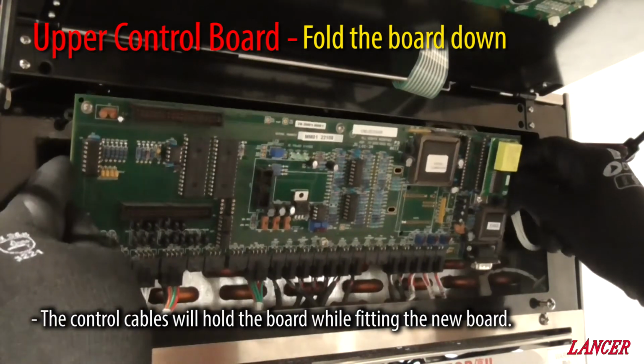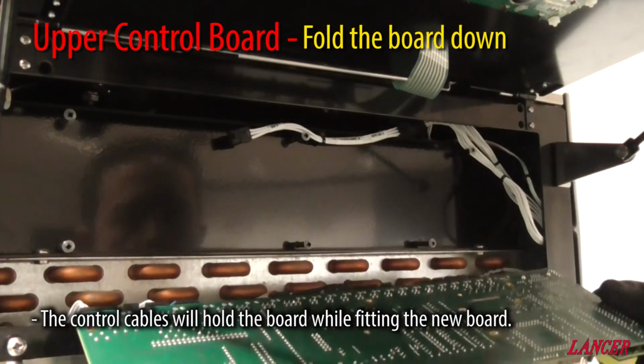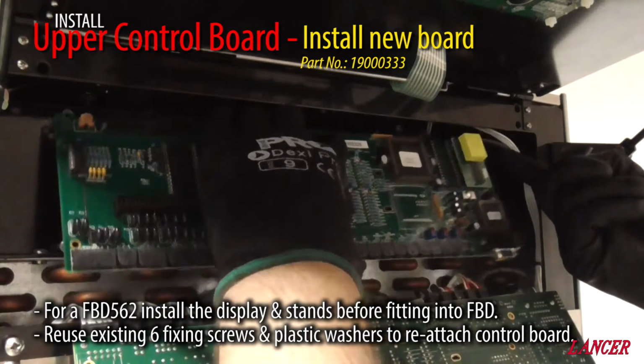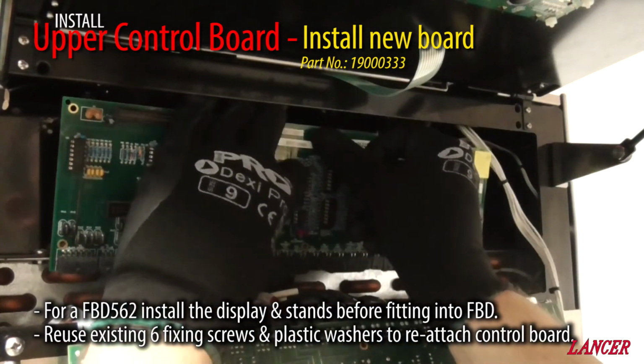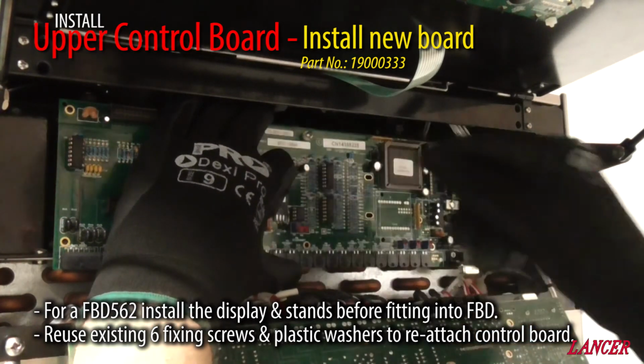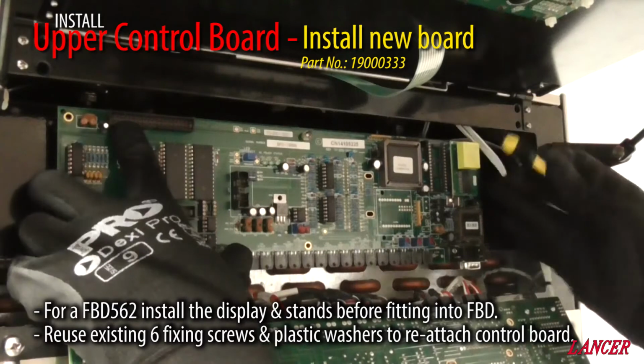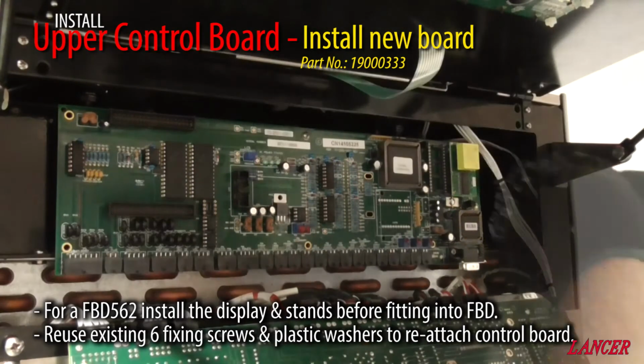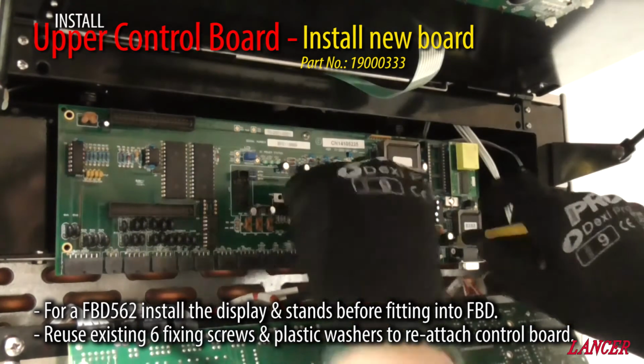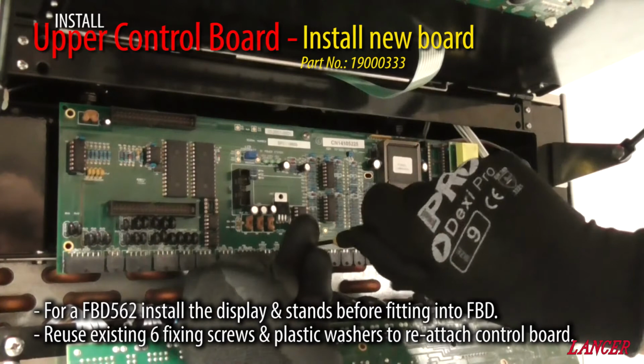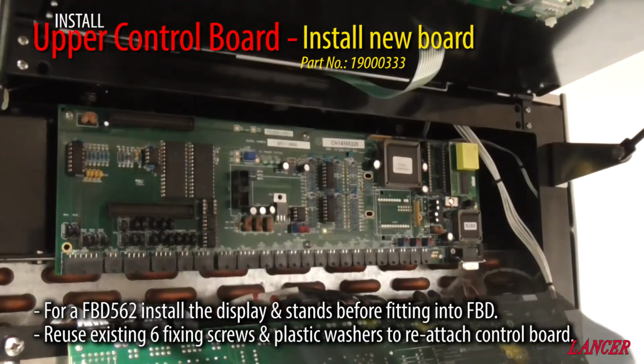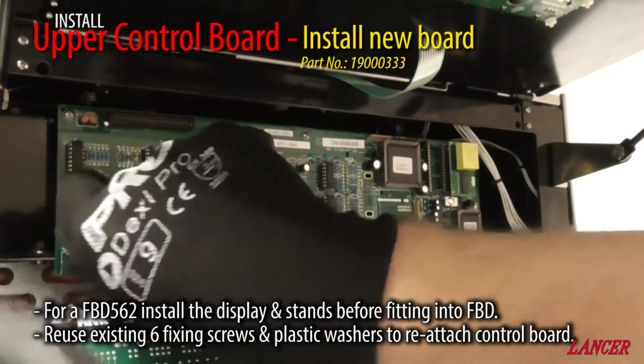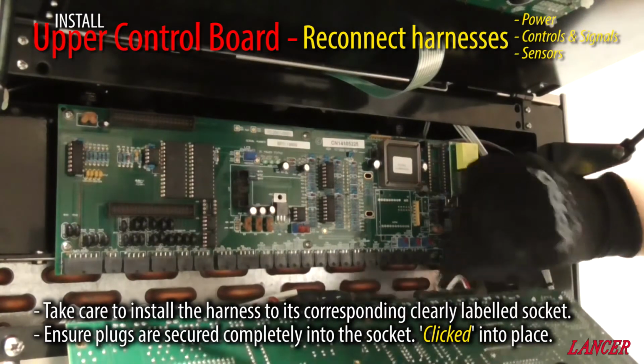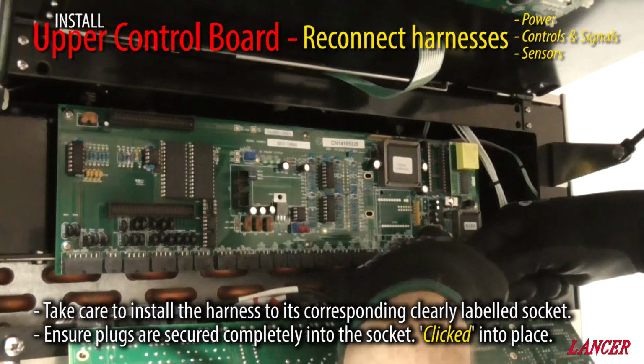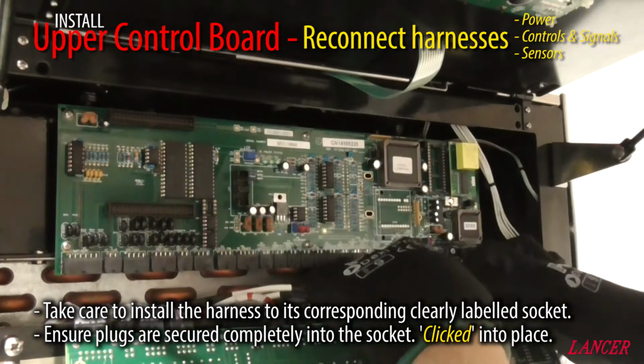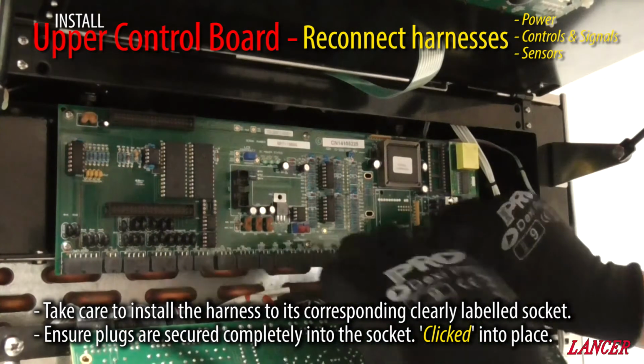Lift out the old board and fold it down, the cables will hold it, and then install the new upper control board reusing the screws and washers from the previous board. We need to reconnect the harness for the power, control and sensors. Please take care to ensure that they're connected into the correct location and that the plugs are securely latched back into place.